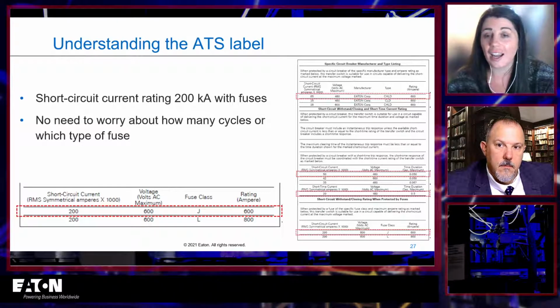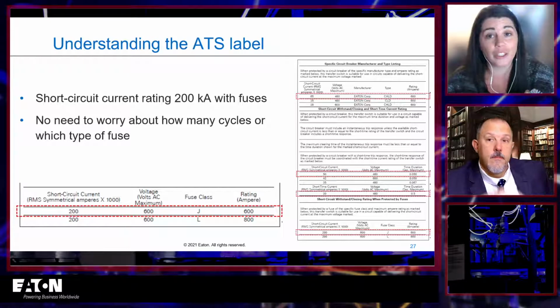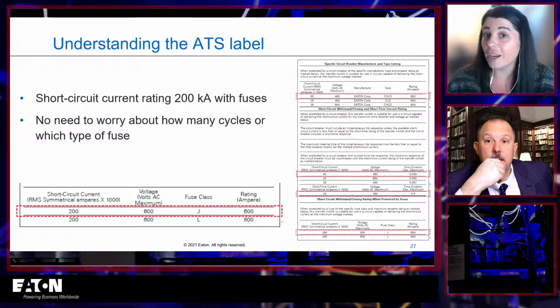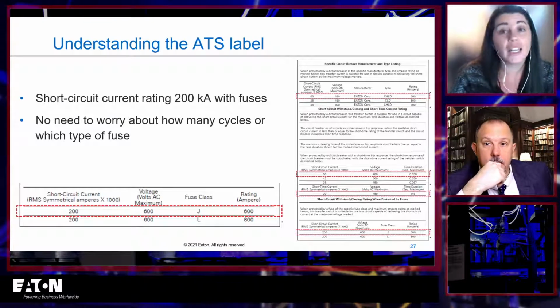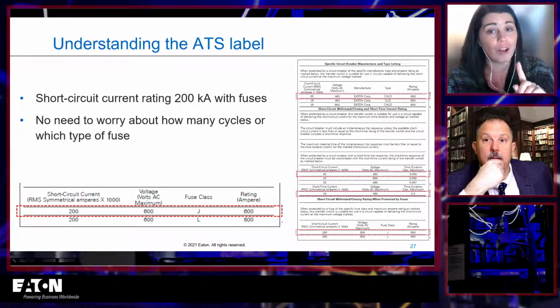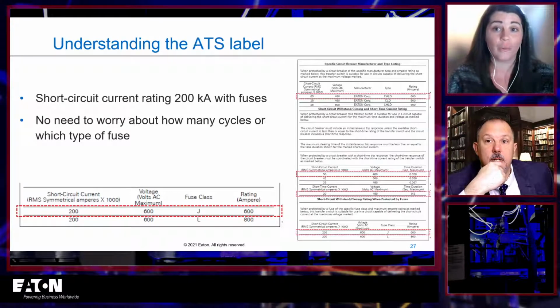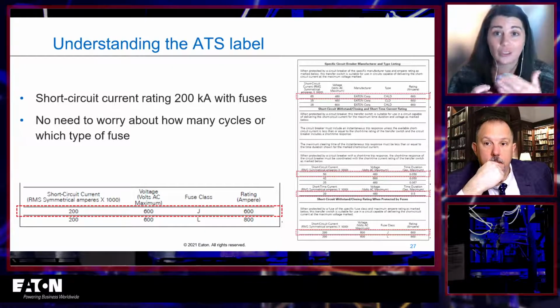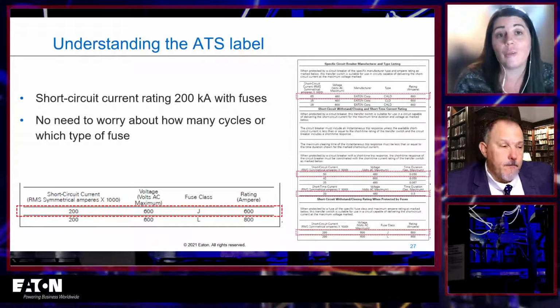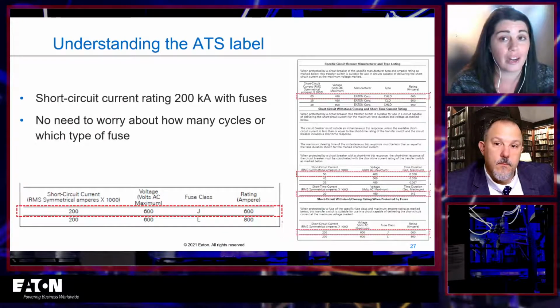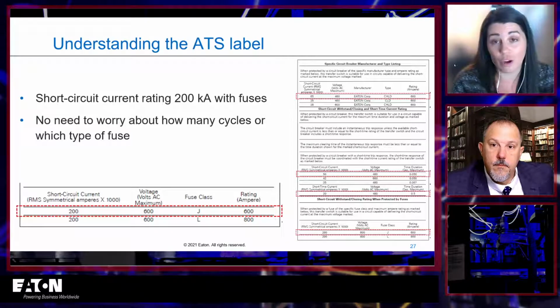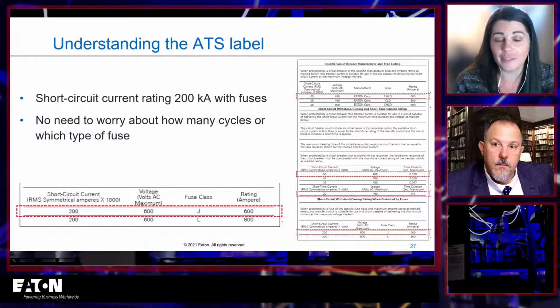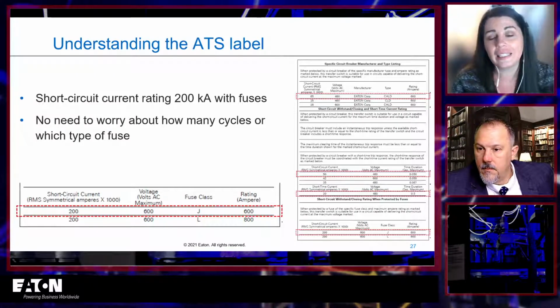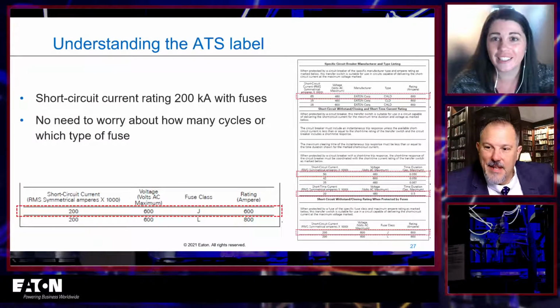An ATS can have 2 separate feeds, right? You can have one from normal, you can have one from alternate. If it's not the same device, you might have 2 different short circuit current ratings. And that's okay, because you're going to have 2 different available fault currents, one from normal and one from alternate. So you want to just make sure that those all match up. But you might have 2 short circuit current ratings, one from the normal, one from the alternate. So just a little bit of uniqueness to a transfer switch.